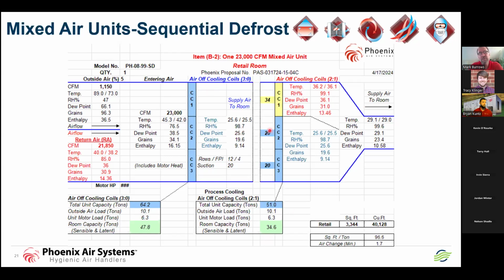Does that mean we're going to frost the coil? Absolutely, but we want to control that. So on the left-hand side of the dashed line, you see CC 1, 2, and 3. Those are nothing more than 3 individual stack coils, each with its own drain pan. In the days of old, people would actually put face and bypass dampers by the coils, or they would try to put hot gas and all this other stuff.